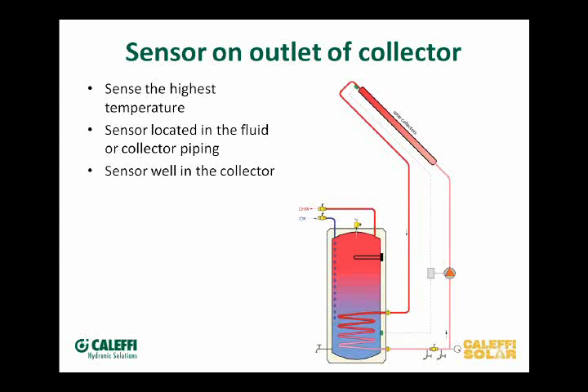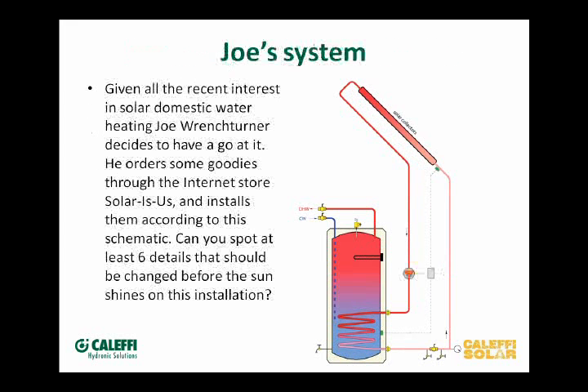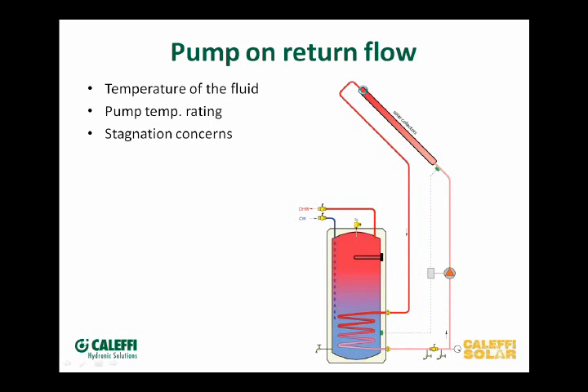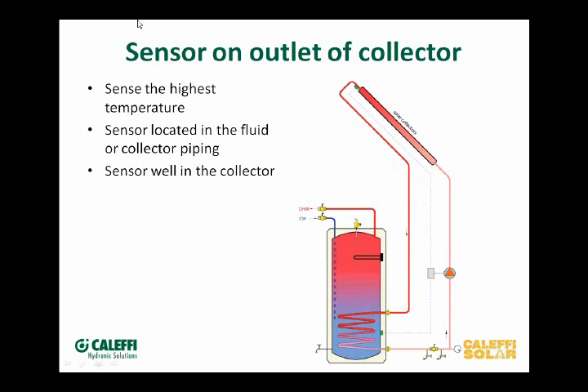The next thing is the location of the sensor. In the mistake drawing, the sensor is on the bottom of the collector — the cold side, because the fluid is coming from the tank being pumped up through the collector. That's not going to accurately read what's going on inside that collector. The sensor really needs to be at the hottest point in the array, which is on the discharge piping or near the top of the collector.